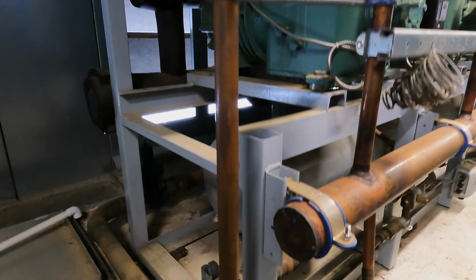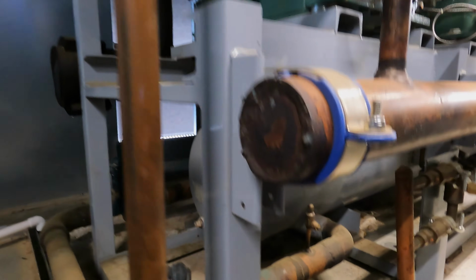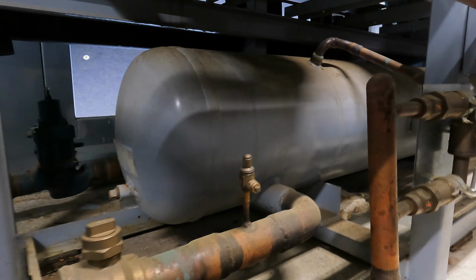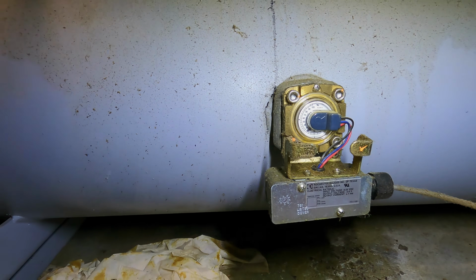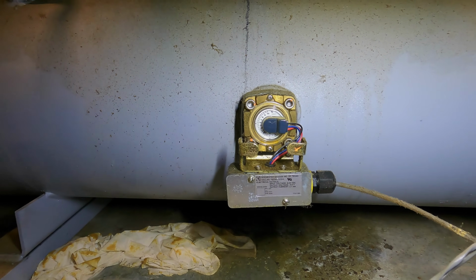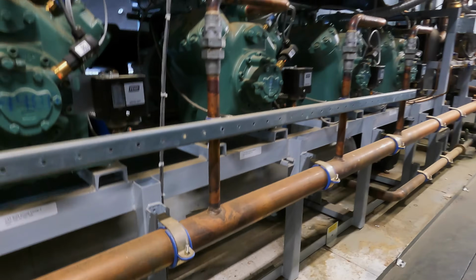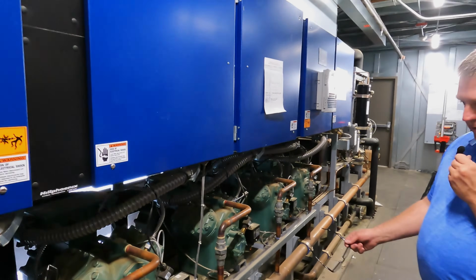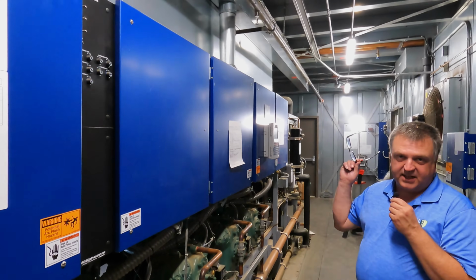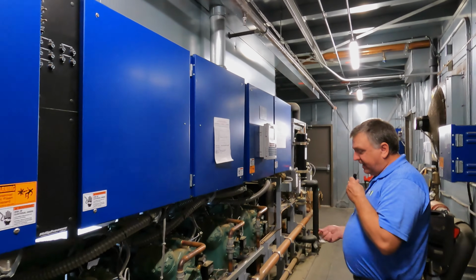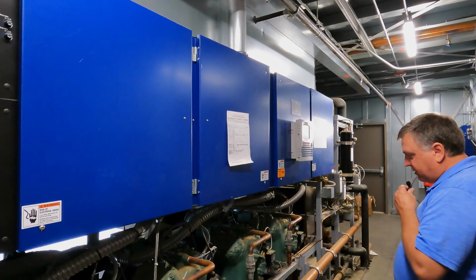During normal conditions, 100% liquid is coming into our receiver. That's what this big tank is. It's got an indicator to tell us how much liquid is in there. Not a very big one, comparatively speaking. There's no way I could pump this whole system down into that because of the size of the condensers that are out there. But that's basically what it is. It holds our extra liquid.